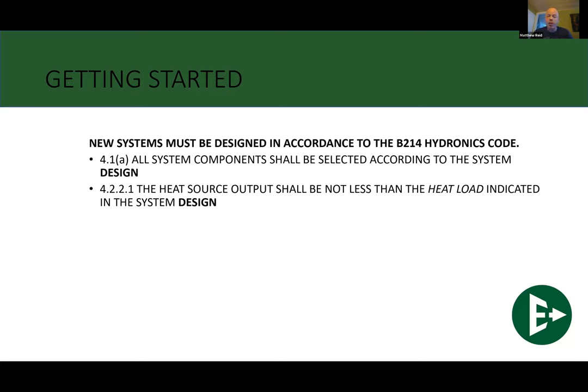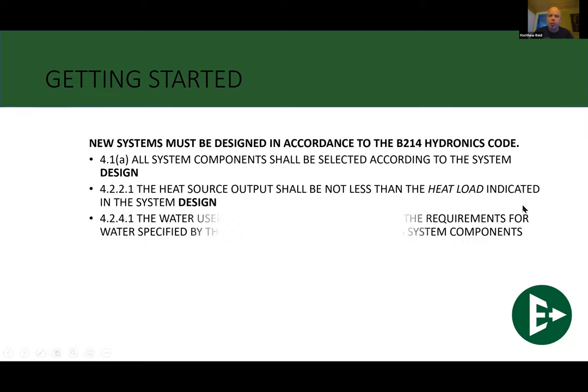It does sometimes even get colder than the coldest day of the year for the design layout. So by undersizing the boiler, even by a little bit, if the temperature does drop significantly, you can be doing a pretty big disservice to the homeowner. Now, when we're talking about BTUs going into a home, we're talking about tens of thousands of these things going in. So a difference of 5,000 or so is not going to be a huge impact. But nobody wants that call from the homeowner that their boilers are running constantly and they can't get the house up to temperature. Nobody wants that. So size the boiler appropriately.